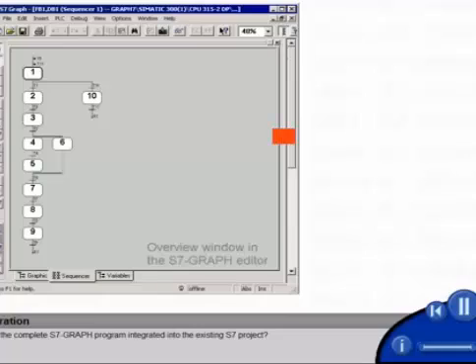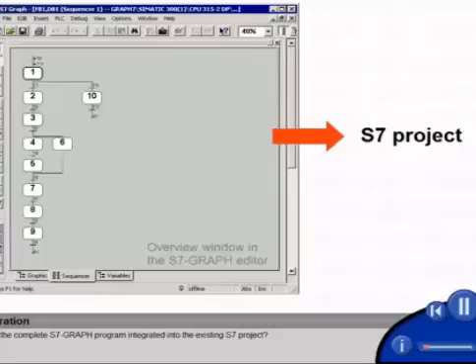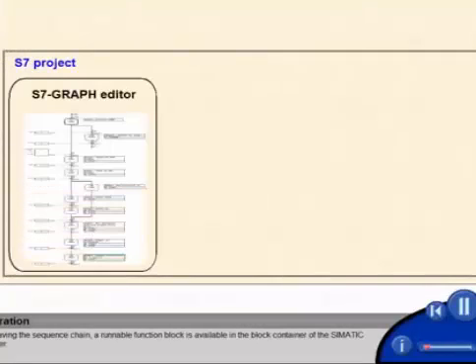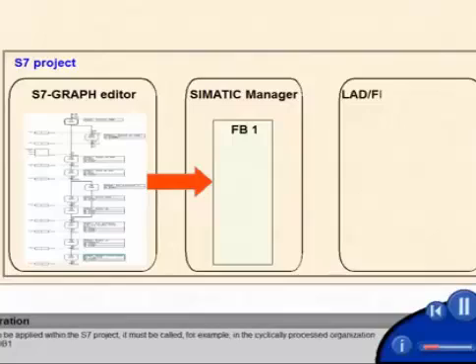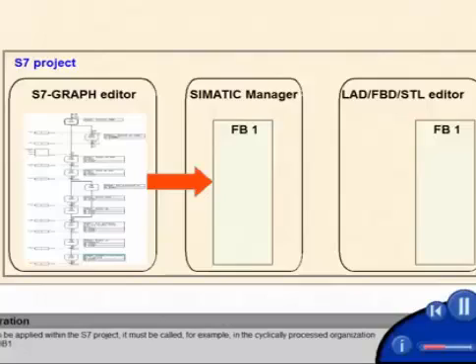How is the complete S7 graph program integrated into the existing S7 project? After saving the sequence chain, a runnable function block is available in the block container of the SIMATIC Manager. For it to be applied within the S7 project, it must be called, for example, in the cyclically processed organization block OB1.